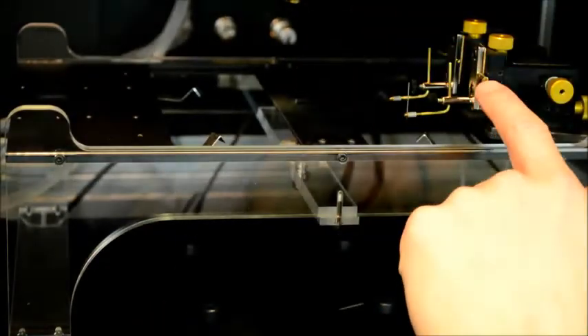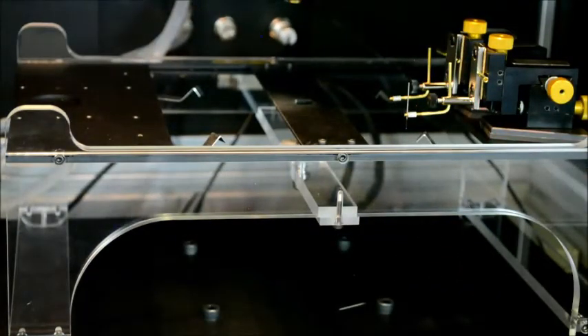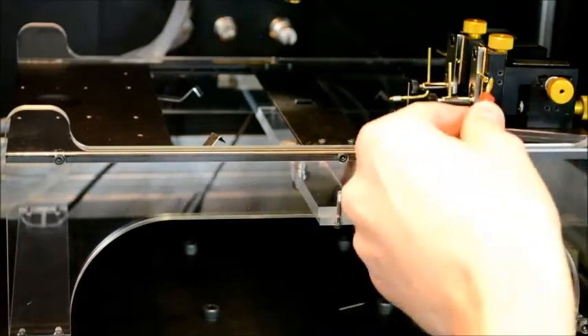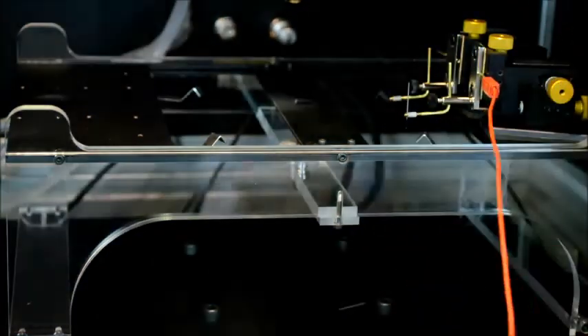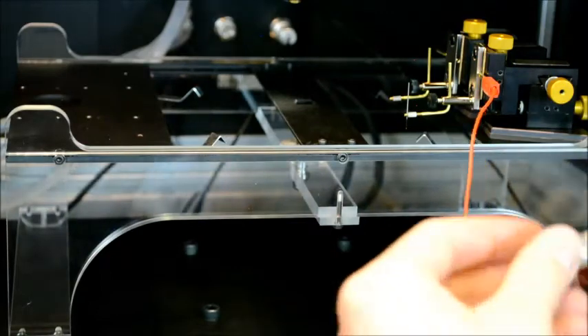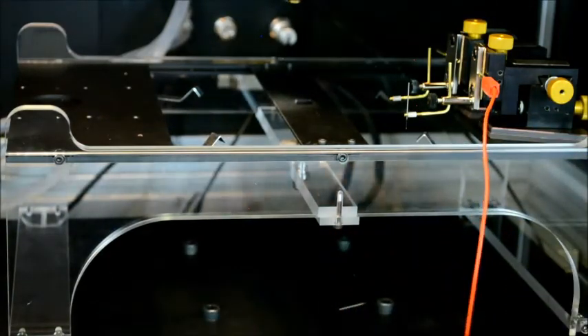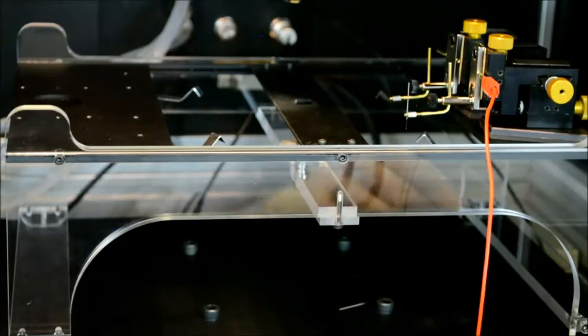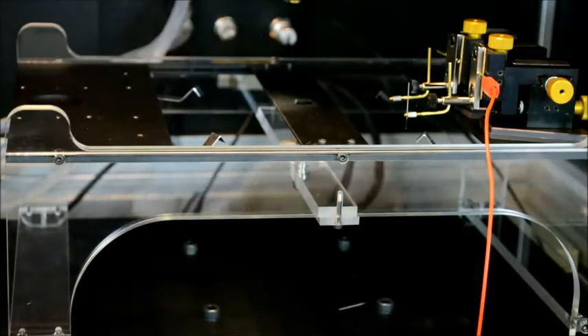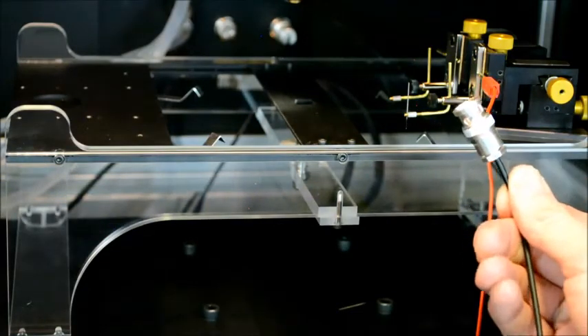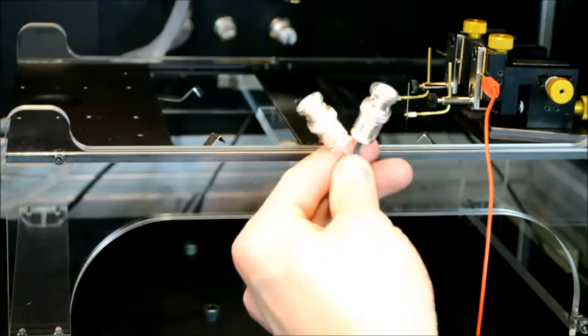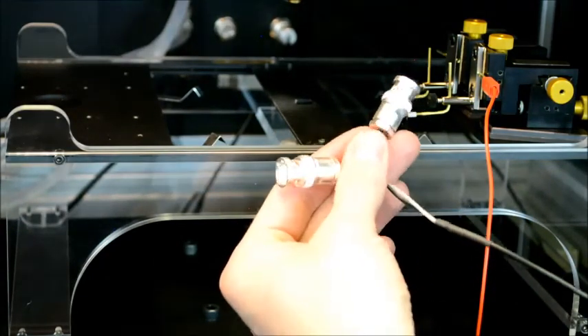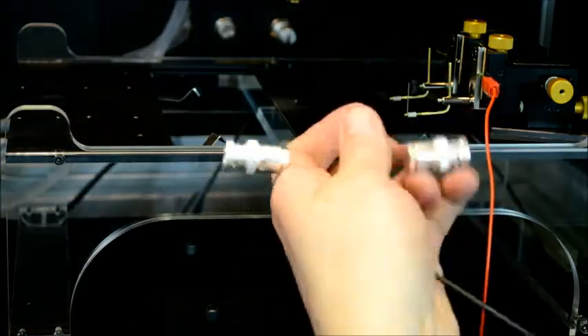Electrical connection to these 2 probes is made from a side connector port, and for each a cable with a small connector terminating in a BNC connector is provided. These 2 probes should be connected to the auxiliary 1 and auxiliary 2 left-hand BNC ports on the rear connection panel. The other side should be connected to a cable provided having 1 BNC connector to input to the 497 preamplifier and 2 BNC cables to connect to 1 probe through auxiliary 1 and the other probe through auxiliary 2.